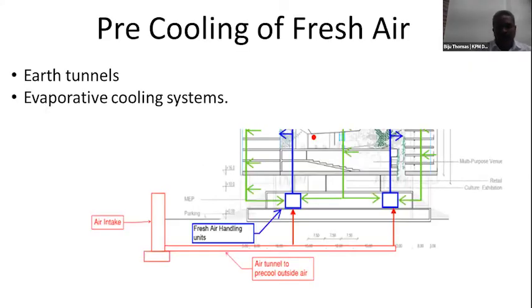Next is how do we pre-cool the fresh air? The speakers before me, Mr. Vikram Murthy, Mr. Subramaniam, and Mr. Debashis, already touched on this topic. As indicated by all the speakers before, if we can use water as a refrigerant for cooling the fresh air, and maybe use earth tunnels for cooling the air, this will help bring down the HVAC loads to a great extent. We are trying this out in one of our projects in the Middle East, where the climate is basically dry, using a combination of earth tunnels and evaporative systems.